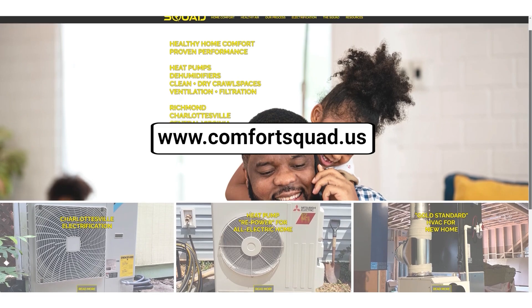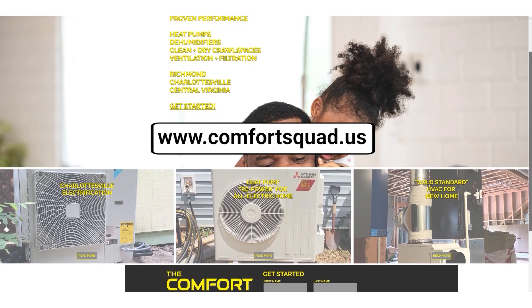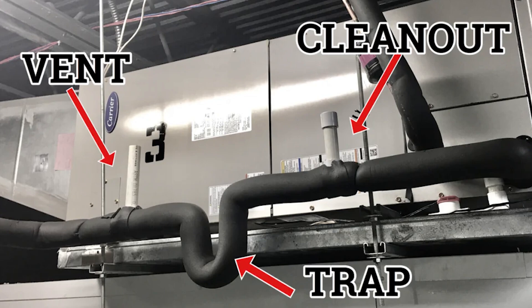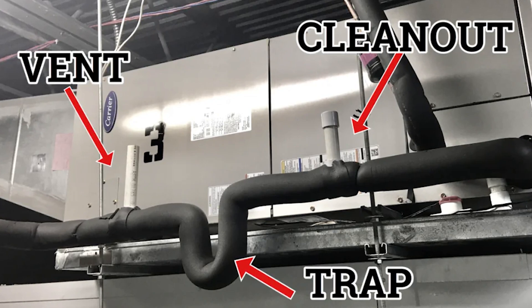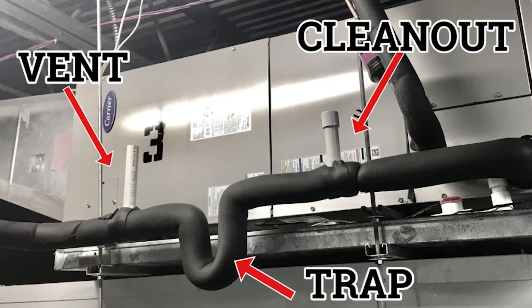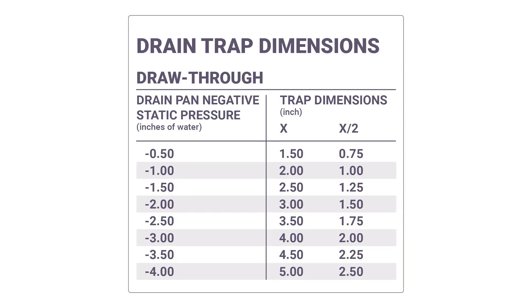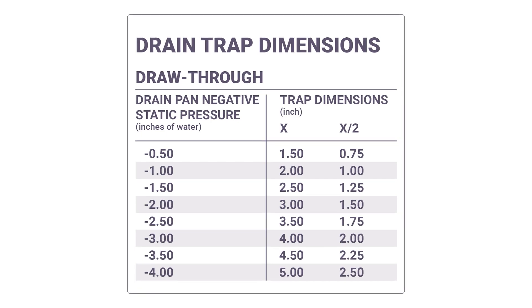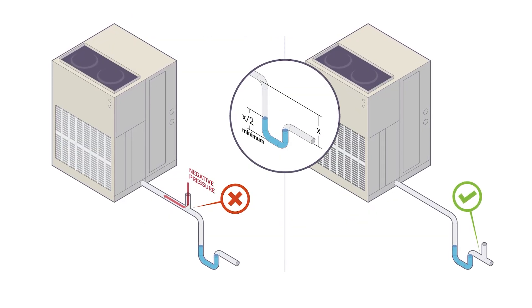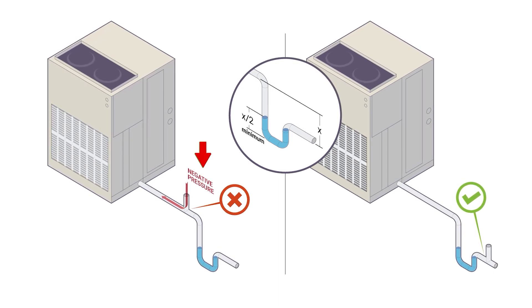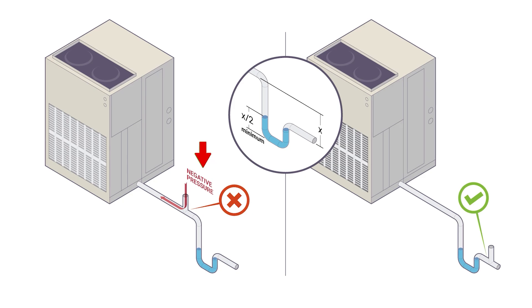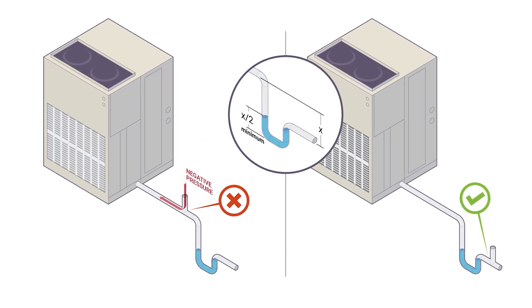We got this question from Steven about condensate trap depth. Steven with the Comfort Squad in Charlottesville, Virginia has a question regarding condensate traps. They've had a number of nuisance calls in the last couple of weeks on retrofit jobs where they couldn't get the static below about one inch. The high static pressure in the air handler is creating a high negative pressure at the drain trap, pulling enough water into the pan to overflow the secondary switch.